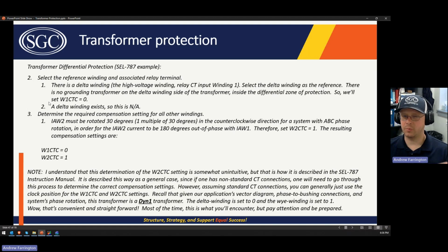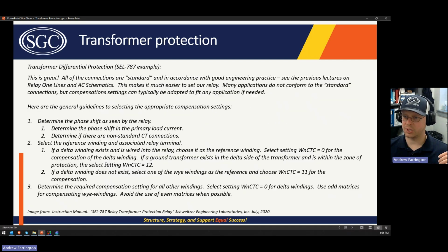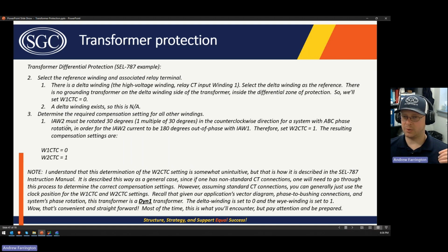So here, I guess I'll read what the relay manual says and then why I think of it differently. The way that the manual tells you to select the compensation settings is, well, we're going to select the delta winding with a setting of 0, and then that step 3 that we just covered here, the manual says to determine that IAW2 must be rotated 30 degrees, which is one multiple of 30 degrees, in the counterclockwise direction for a system with A, B, C phase rotation in order for IAW2 current to be 180 degrees out of phase with IAW1, therefore set W2CTC equals 1.